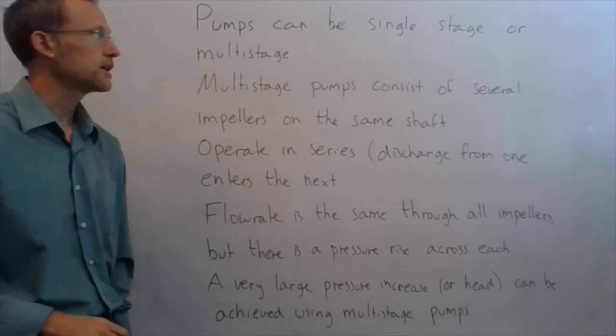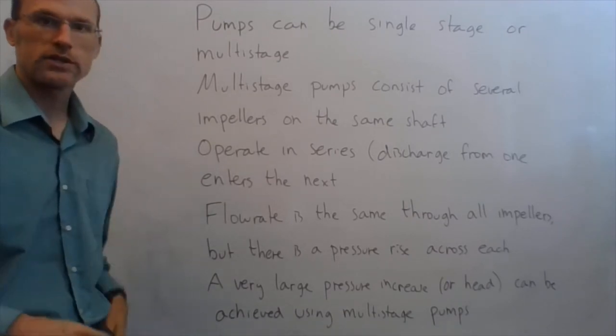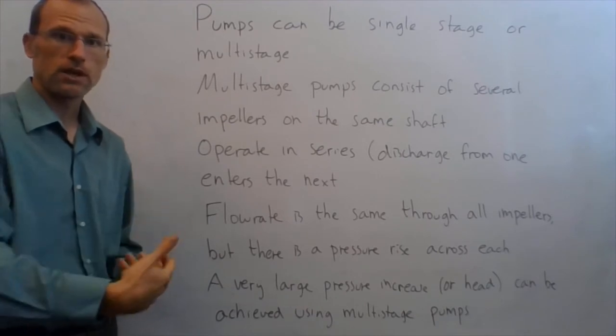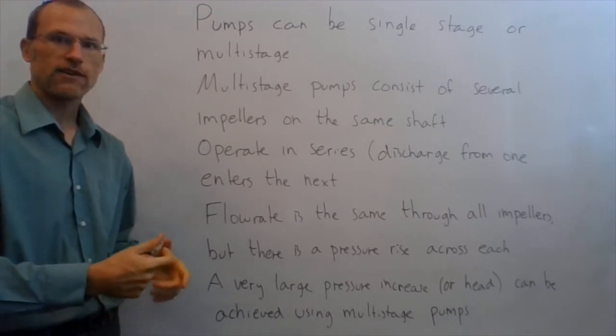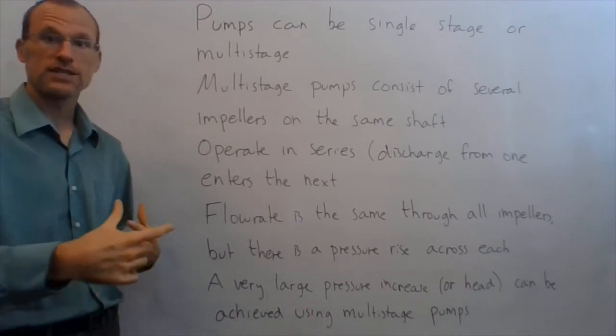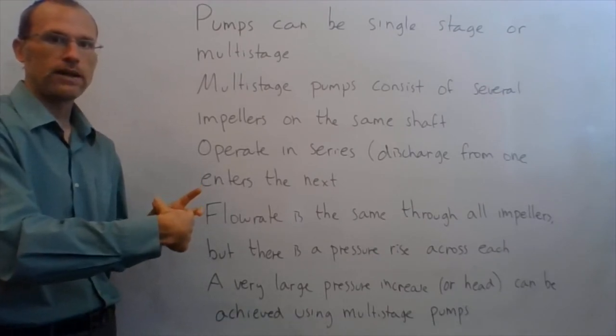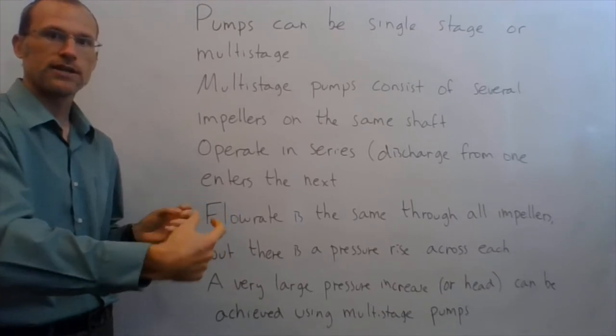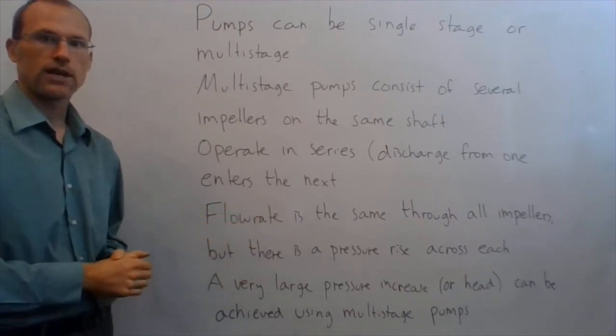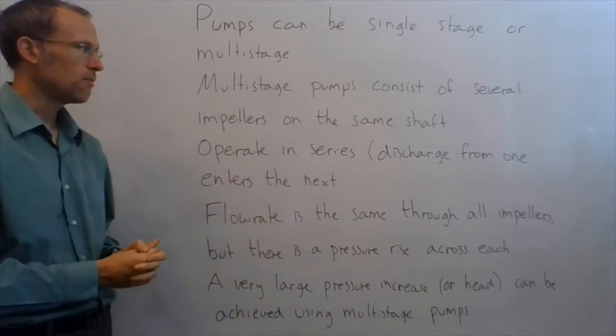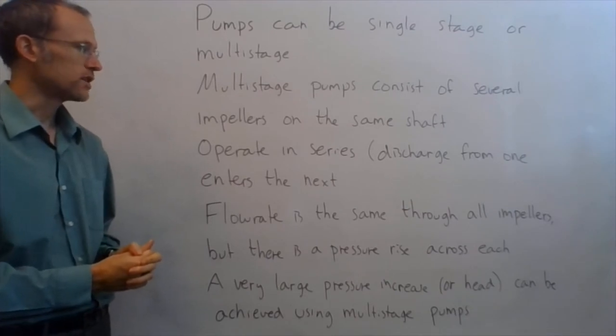So these pumps can be either single stage or multi-stage, so single stage is obviously just a single pump, single impeller system. Multi-stage you have multiple impellers on the same shaft, so as it comes through, it goes through one impeller, and the discharge from that enters the next impeller, discharge from that enter the next impeller, so you have this multi-stage pump system, discharge from one enters the next.